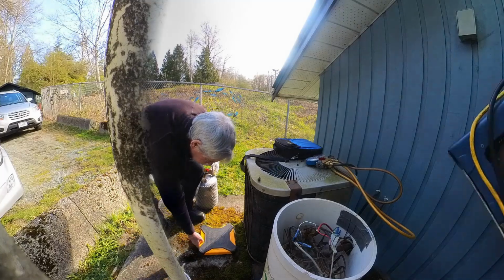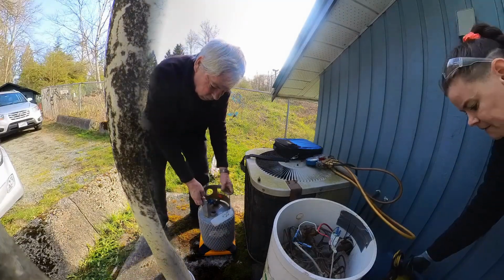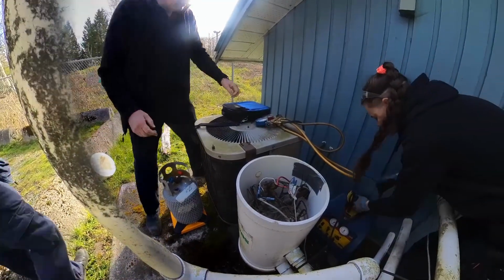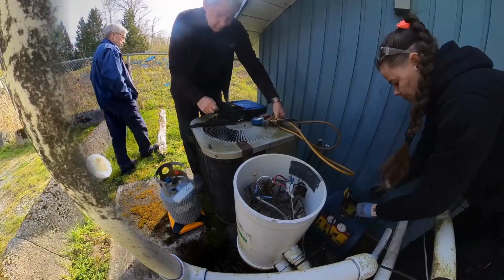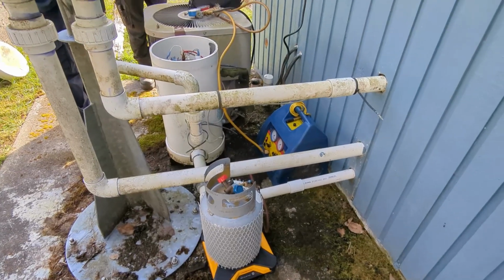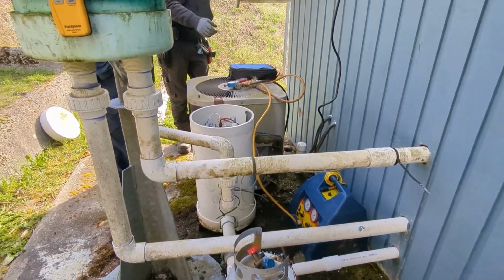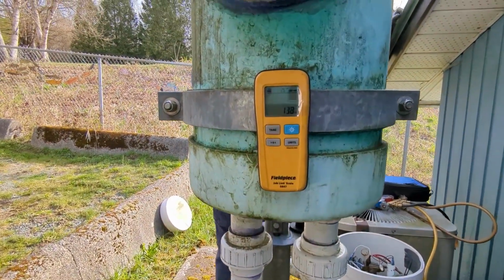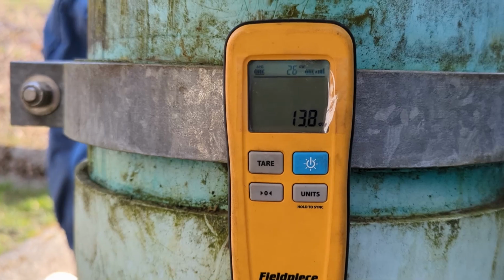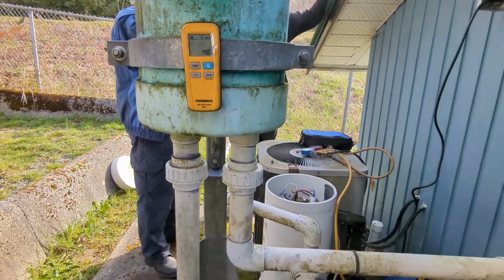separate from each other. And then we would pressurize both of the systems. We would pressurize the condensing unit and we would pressurize the heat exchanger. Left them under pressure, see which one dropped, if any. In order to do that, we had to recover the remaining refrigerant so that we could separate the systems. But we were also kind of curious to see how much refrigerant came out of it compared to what's on the nameplate. If I'm not mistaken, I think we were looking for 70 ounces, and we ended up pulling out 23 only.